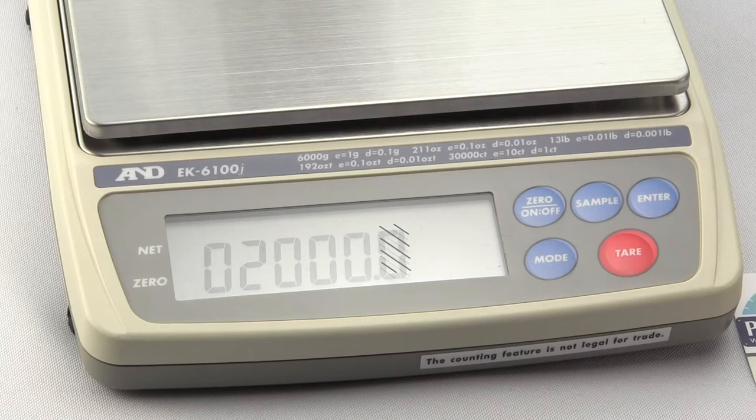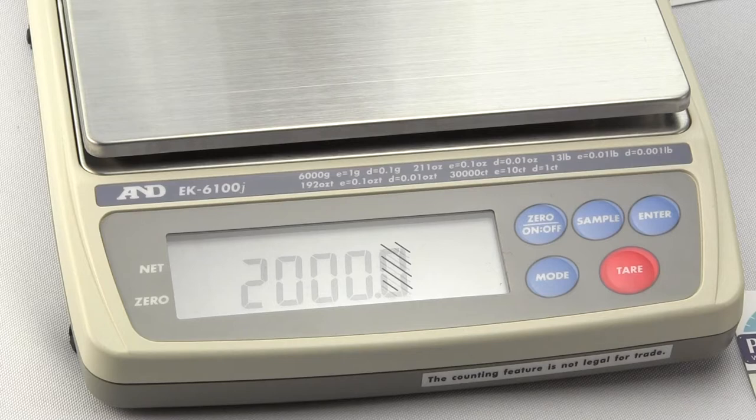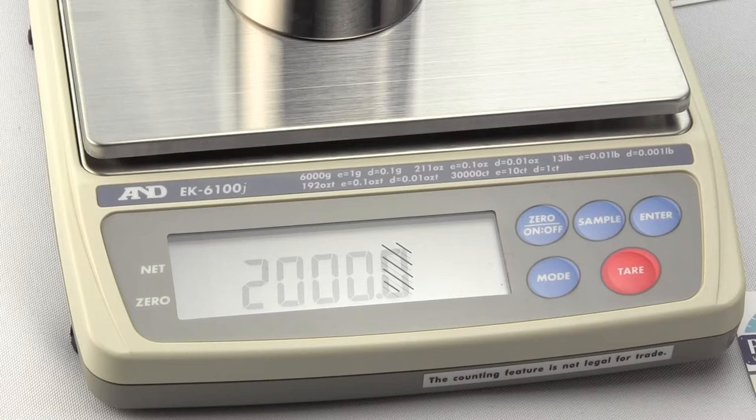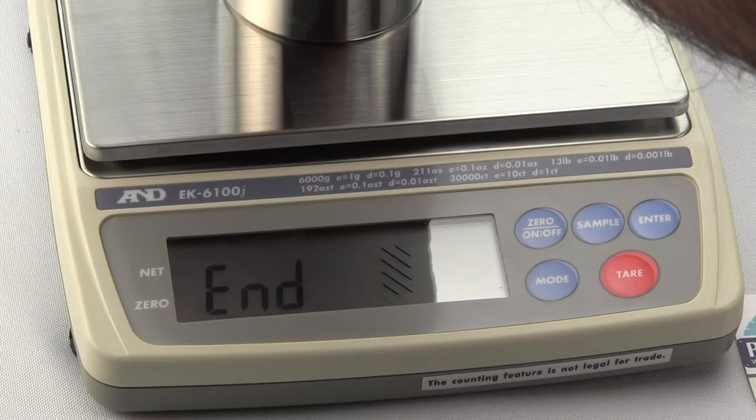It goes back to CAL 0. We hit the ENTER key. Stores the value with no weight on the platform. Now it flashes 2,000. Put a 2,000 gram weight in the center of the platform. Press the ENTER key. It stores that value. END comes up. We remove the weight from the platform. Hit the MODE key.